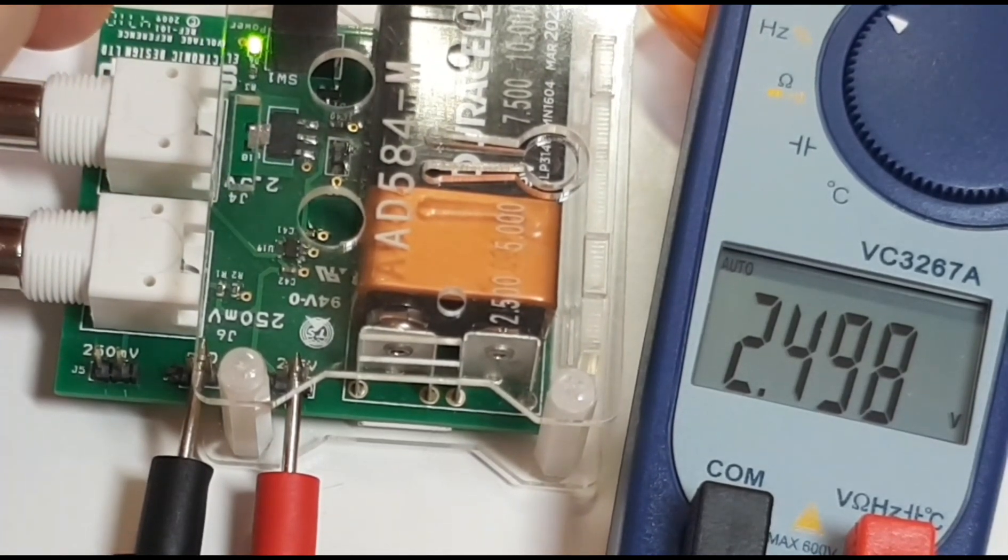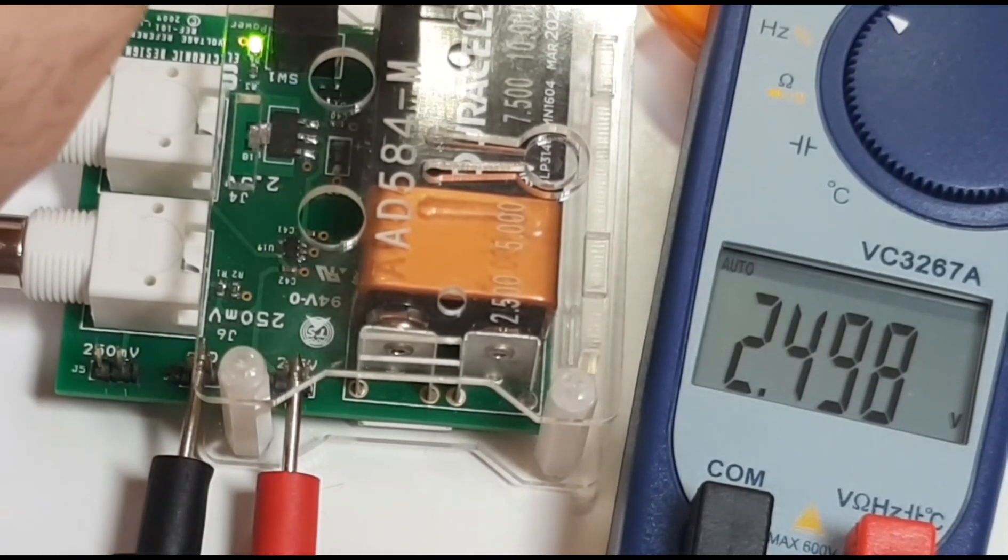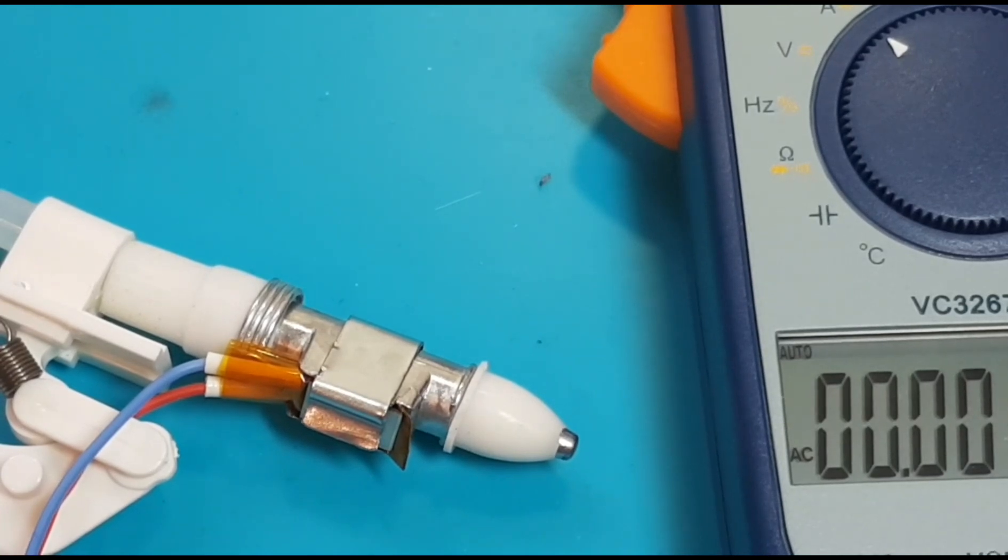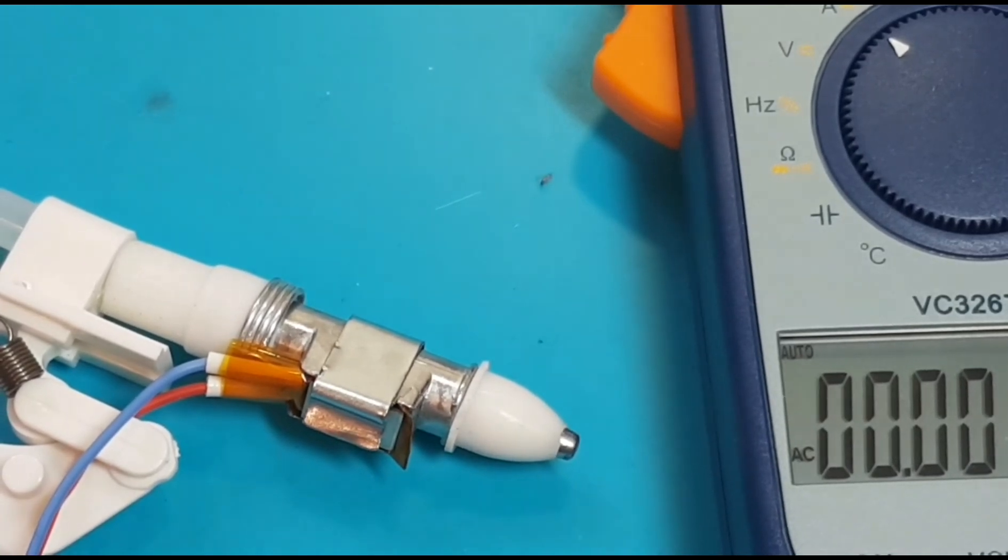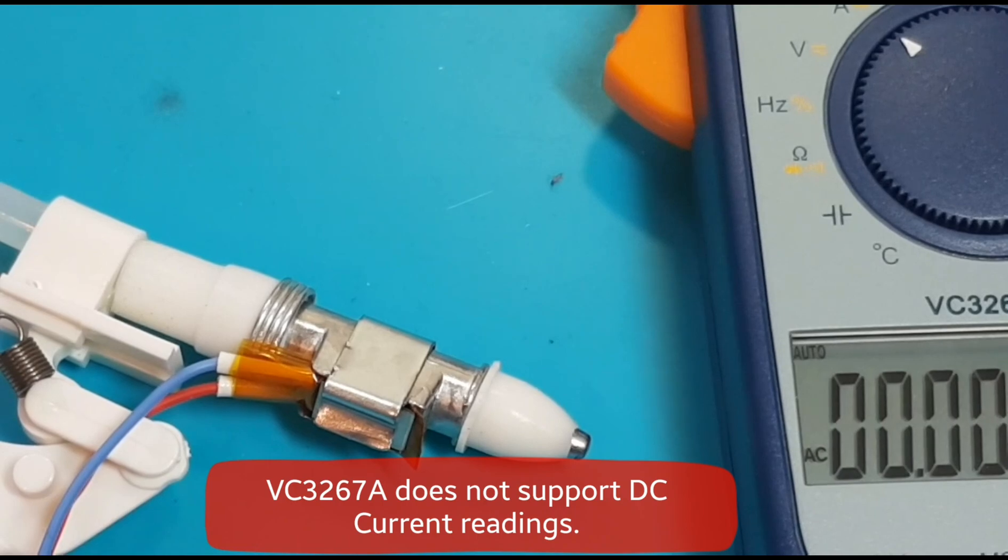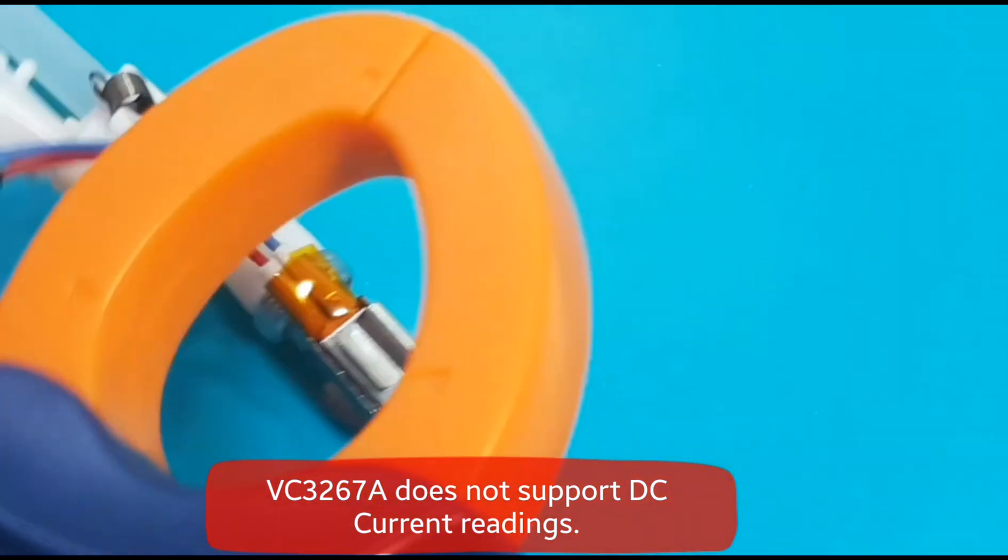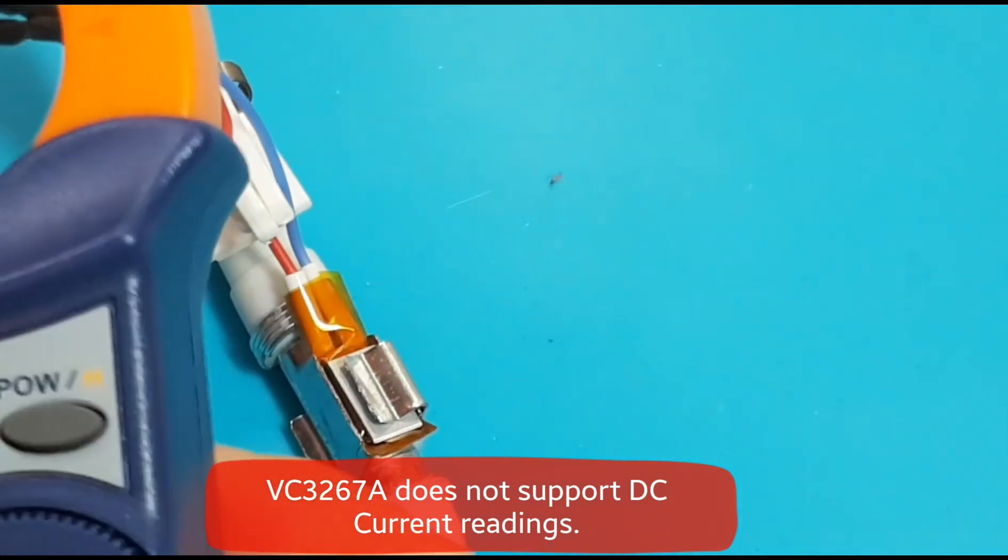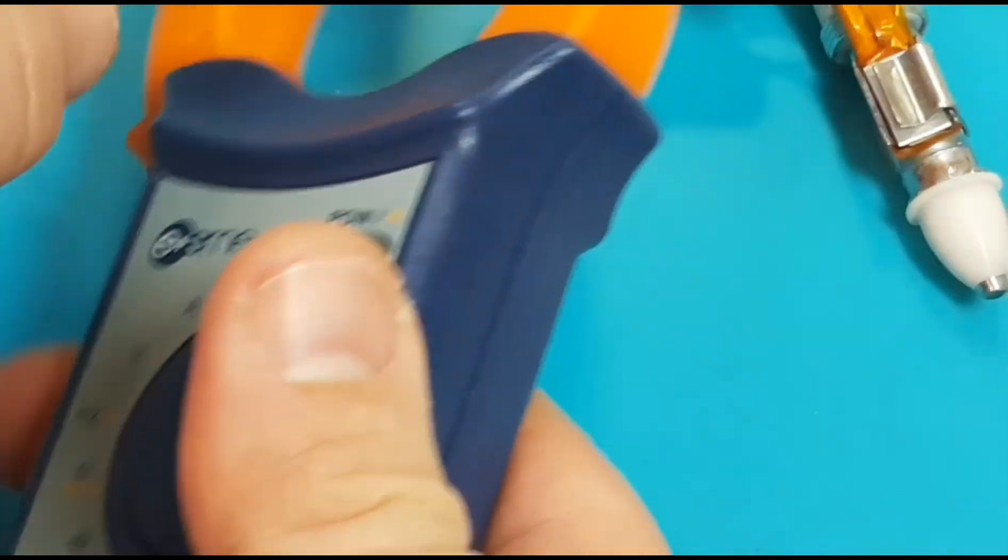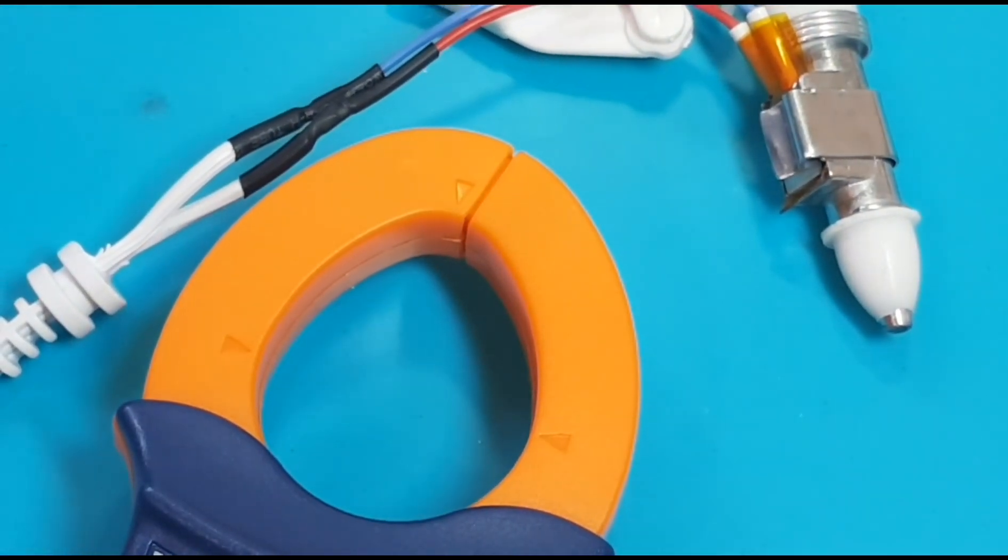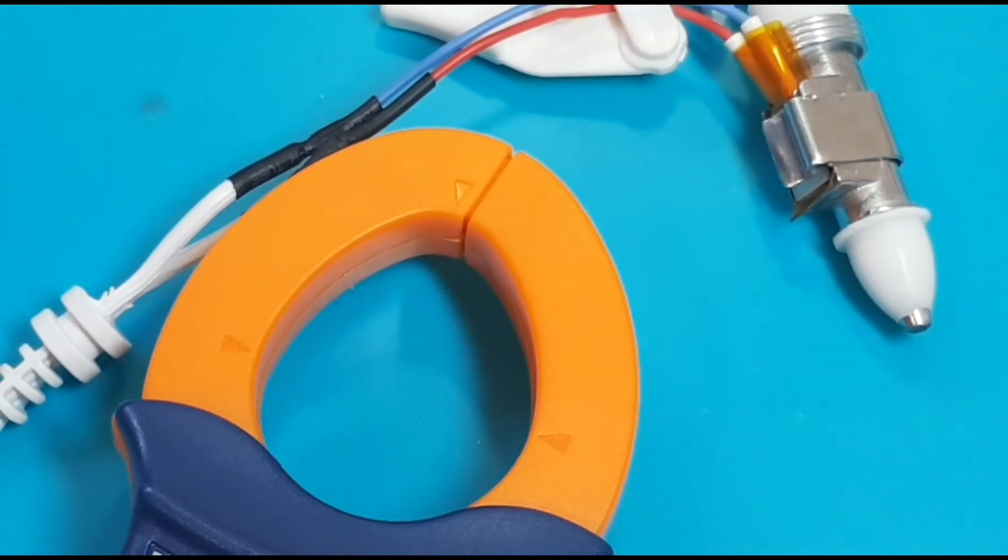So next up is AC current. Now most people when they're using a clamp meter for the first time don't realize that you can't simply take your clamp meter, put it onto your current mode, and go ahead and get a reading. It's just not going to work. So the reason why that mystifies so many people, it's actually relatively simple. It's because the current running through both wires are actually canceling out the induction into the coil.